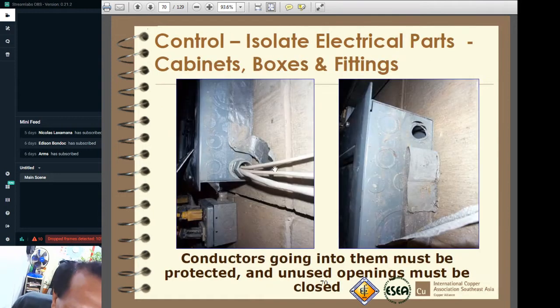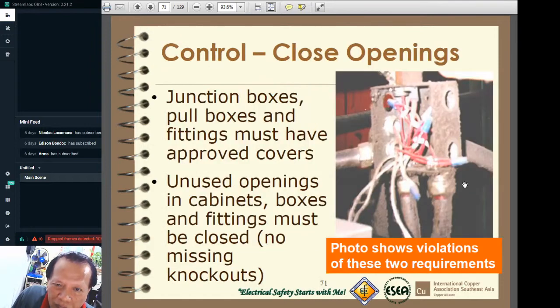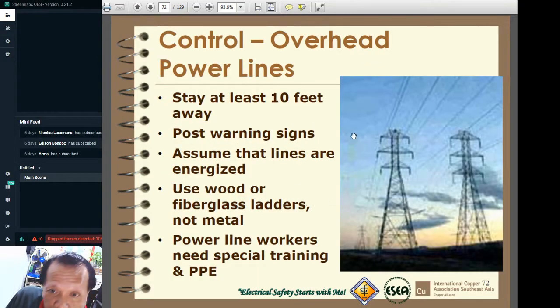Okay, and here you would see uncovered holes. Again, some foreign bodies might enter and might cause grounding or short circuit, so you have to be careful. Again, this one, this metal box, is already rusted, and there are no covers also. Again, that might allow foreign bodies, animals, rats, and others to come close to it or even damage the insulation of the wires. Okay, so they should have covers. Overhead high voltage line, we should keep away from them. Very dangerous. You may never know when the lines would fail and drop down.